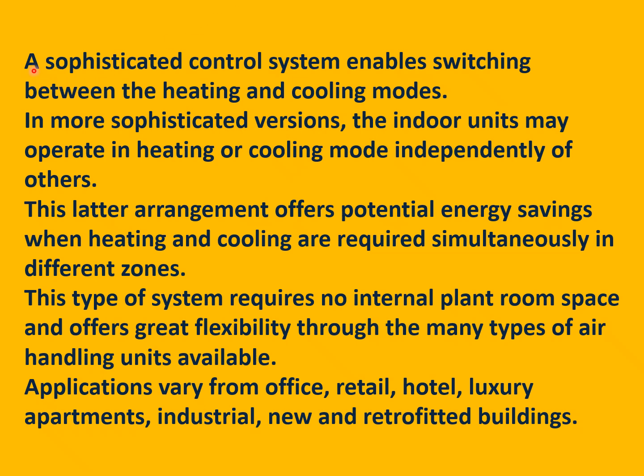Friends, the VRF system requires a sophisticated control that enables switching between heating and cooling modes. In a more sophisticated version, the indoor unit may operate in heating or cooling mode independently of others. That is known as heat recovery. The latter arrangement offers potential energy savings when heating and cooling are required simultaneously in different zones. This type of system requires no internal plant room space and offers great flexibility through the many types of air handling units available. Applications vary from office, retail, hotel, luxury apartments, industrial and new and retrofitted buildings.